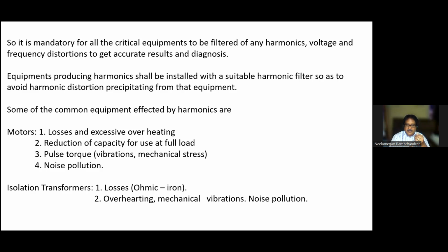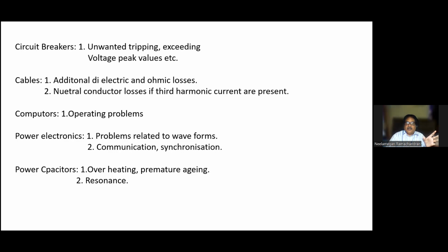Losses, excessive overheating, reduction of capacity for use at full load, torque, noise pollution. In isolation transformers, there is ohmic and iron loss, overheating, mechanical vibration, noise pollution. In circuit breakers, unwanted tripping, exceeding voltage peak values. This is harmonics combined with low voltage. By low voltage I mean 390, 395, 400. In some places, we get this voltage constantly. A voltage of 390 or 400 will not create any problem by itself. But if harmonics are present, the circuit breaker will trip. The circuit breaker service person will come.